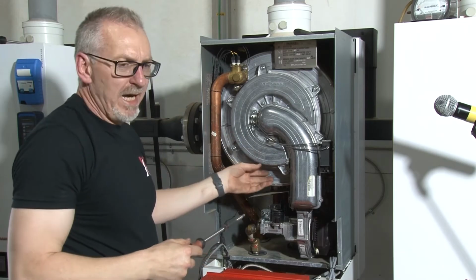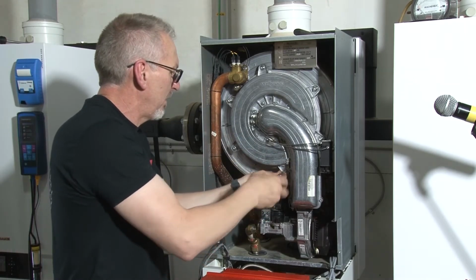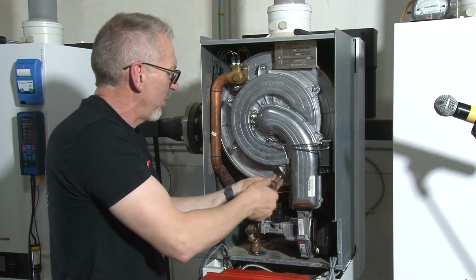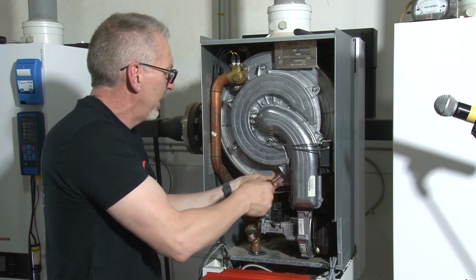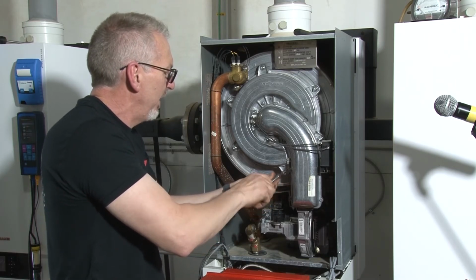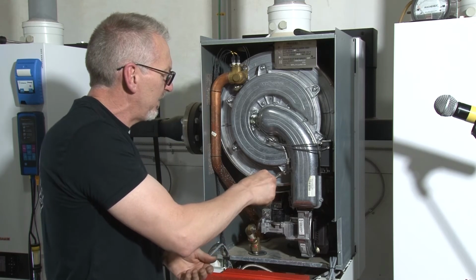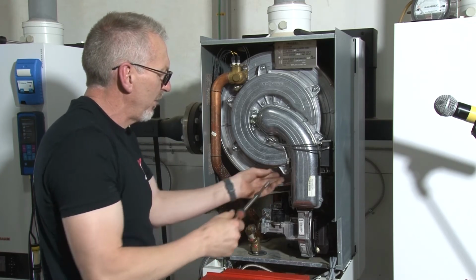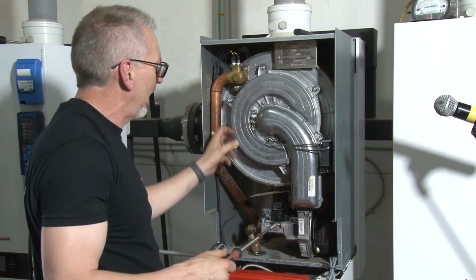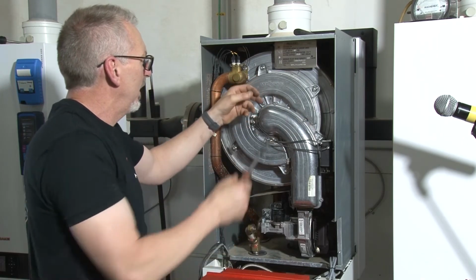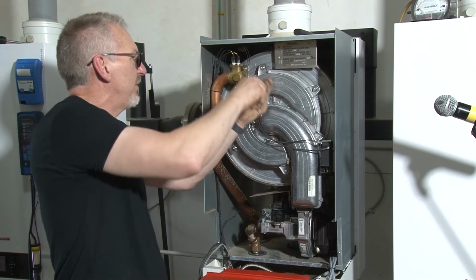5 out of 6 ain't bad. That's not really the truth as far as these burner bolts go. You want to have 6 bolts that are nice and tight here. And notice that when I tighten this up, I'm just giving it a tight and then about a quarter turn just to seal that. This gasket I talked about is doing all the sealing for me. It's doing all the work.